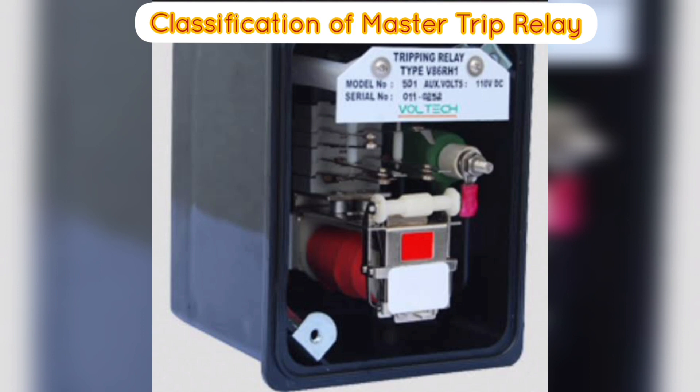Next we learn about the classification of Master Trip Relay. There are three categories of Master Trip Relays based on the fault detection level. Some faults need only annunciation and no tripping, whereas some faults need immediate electrical isolation. The three categories are: 1. Low Level Trip, ANSI Code 86L. 2. Medium Level Trip, ANSI Code 86M. 3. Heavy Level Trip, ANSI Code 86H.